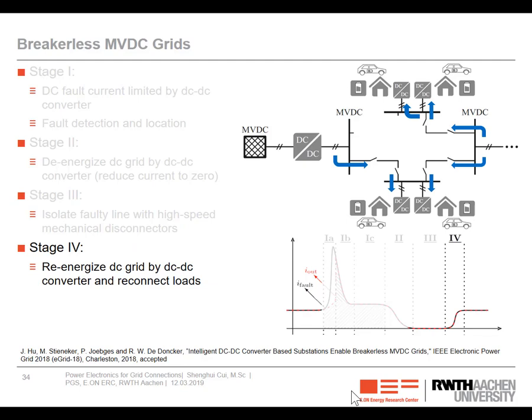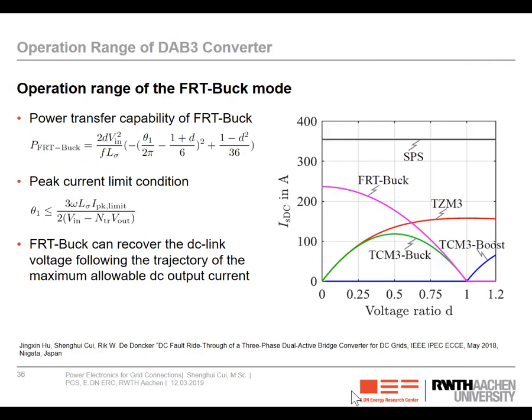And afterwards, we will re-energize the DC grid actively. So this DC converter at first builds up the DC voltage, and then it starts transmitting power again. And how can we do it? Here there's a very interesting figure, which is the DC side current versus the voltage ratio. The voltage ratio D is the output side voltage over the input side voltage. And we know that when a short circuit fault occurs, the output voltage immediately goes to zero. So here the voltage ratio will move to zero.